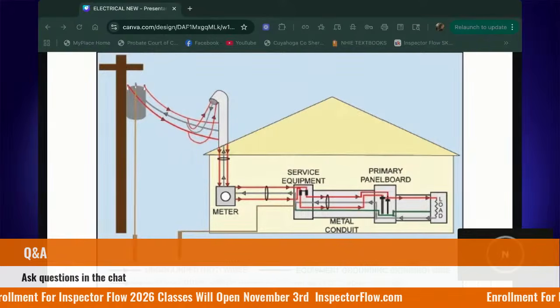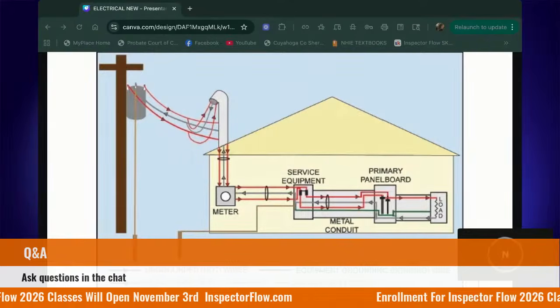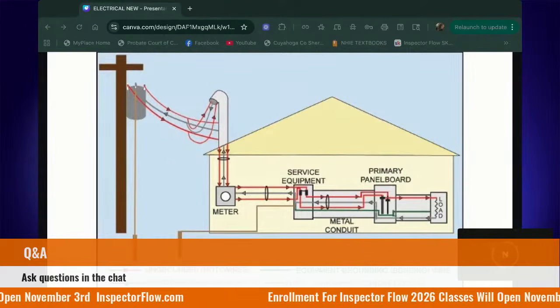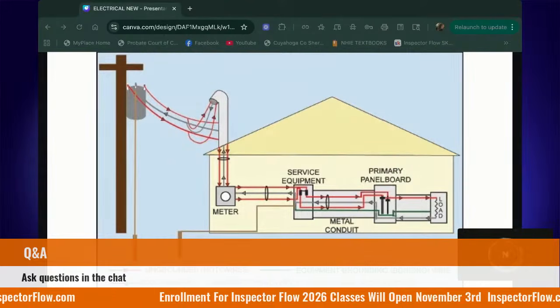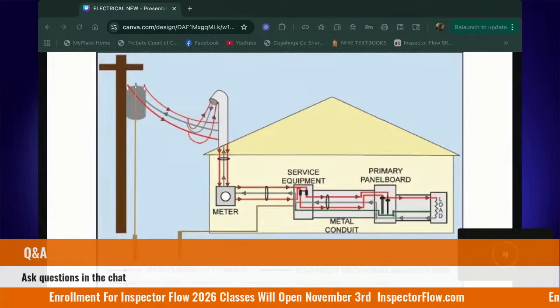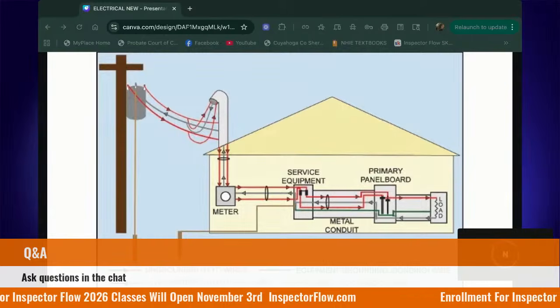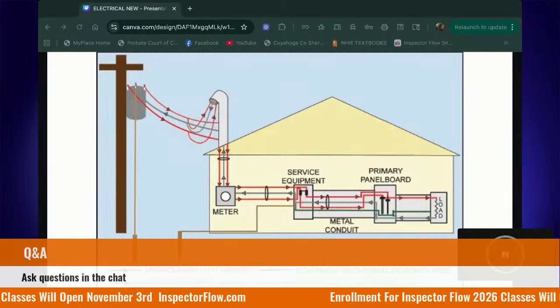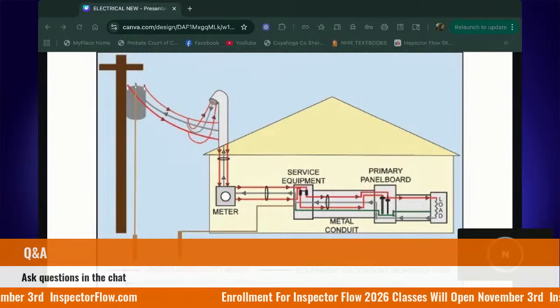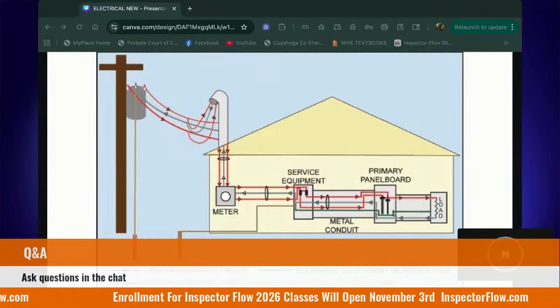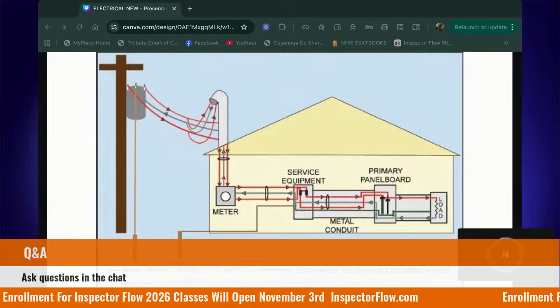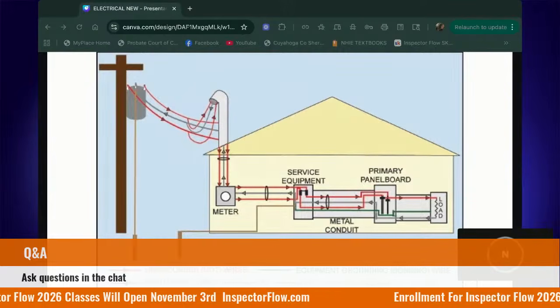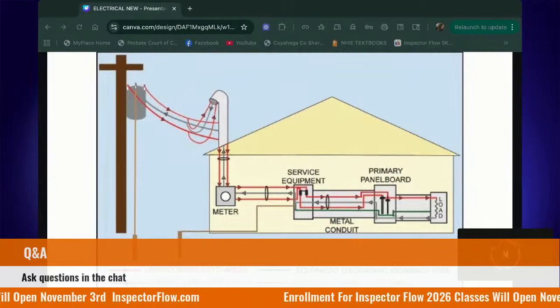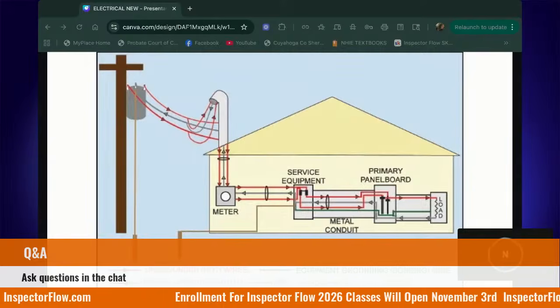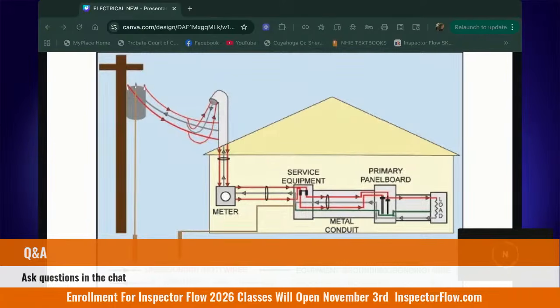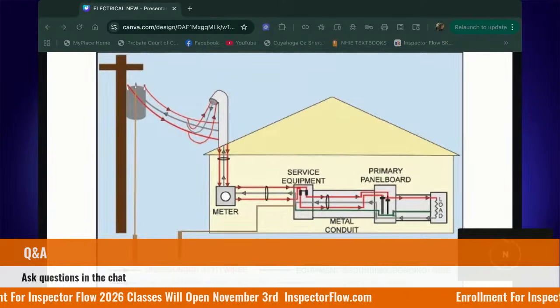What if I have neutrals and grounds on the same bus bar? Would it still be terminating there, as it's bonded? Right? Well, the bonded part just means that the GEC is connected to the bus bar. But if I have a bus bar that has white wires and bare copper wires, could I also find my GEC there?